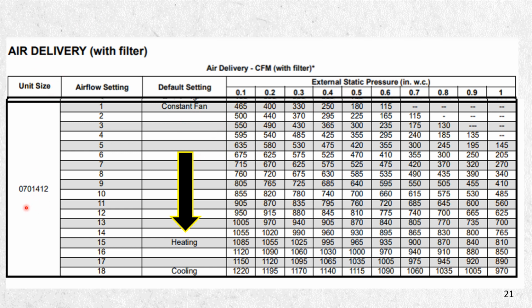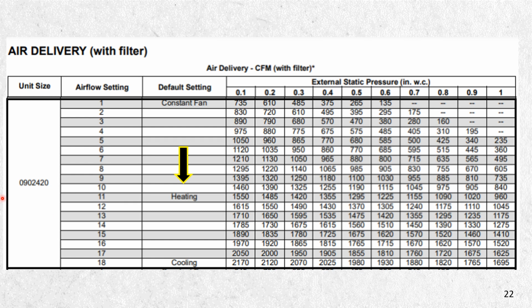But you can look at the different model sizes. Here, this is a 1200, but it's an 070. Heating minimum needs to be from the factory at 15. So keep that in mind when you're looking at these readings. This one is a 090, 2000 CFM, and it's factory set at 11. And also your cooling is at 18. But you can also look here, 2000 CFM. And on the cooling, I can get 2000 right here. If I'm at 0.40 and 18 in cooling, I can still get that 2000 range there.